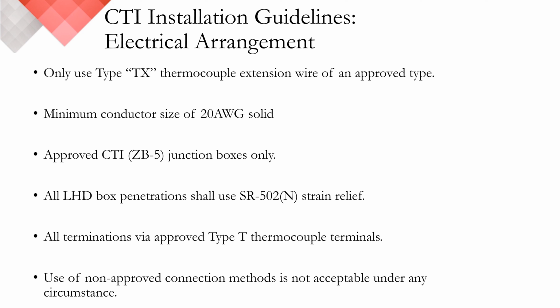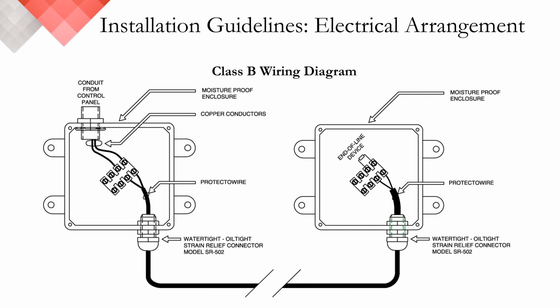If you experience this during your commissioning or testing process, then it's almost certain that you reversed wires somewhere in your run, or you might have a terminal block that's improper. Again, we offer the appropriate junction boxes that have been selected and equipped with the proper terminals to accommodate the CTI system. And here we have a classic illustration of a Class B or Style B wiring.